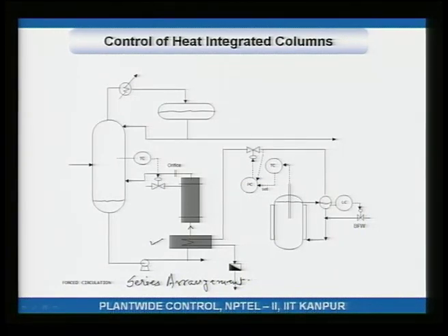And the totalizer here is the steam that is going into the column, or the boil up that is going into the column, because of the way it is designed, it is the total steam. Okay, so one way of controlling, the totalization happens naturally, and I think it should be shown. It's not very well shown in the presentation. So what I would say is, what should be done is, if this is the valve, this is the total boil up that's going into the column. This total boil up is controlled by adjusting the auxiliary steam, and the temperature controller adjusts this steam set point.